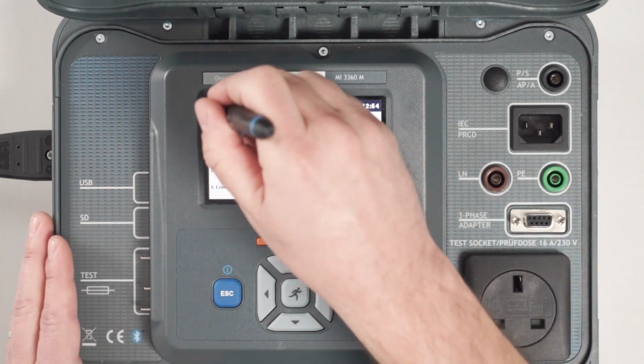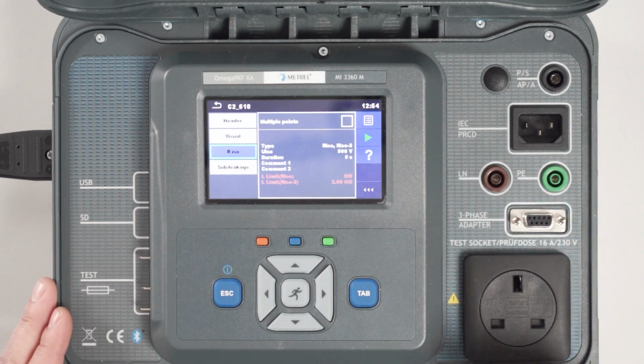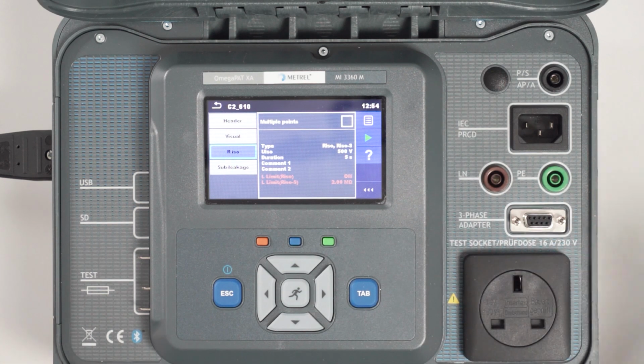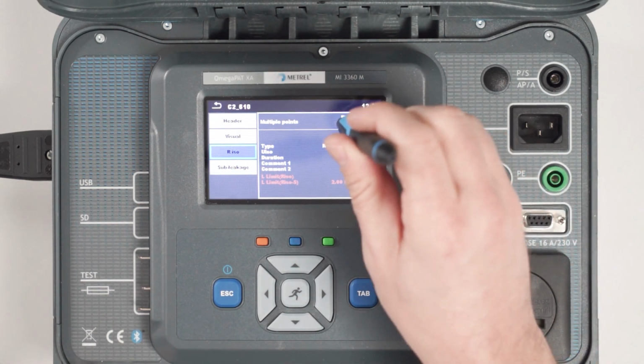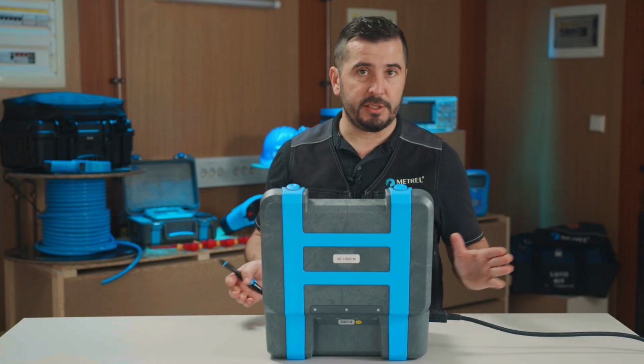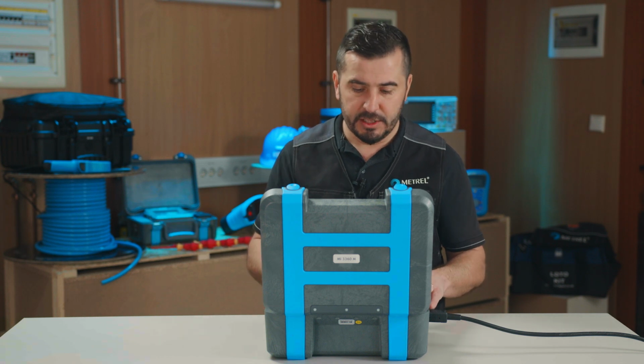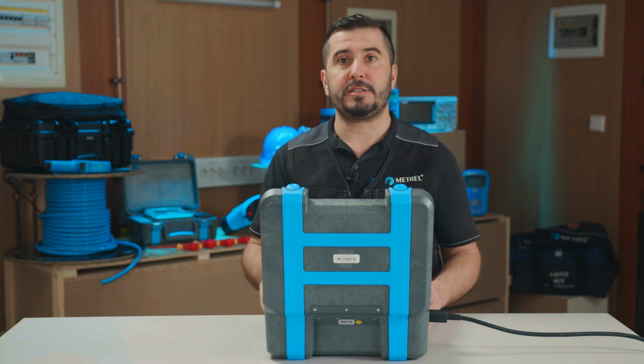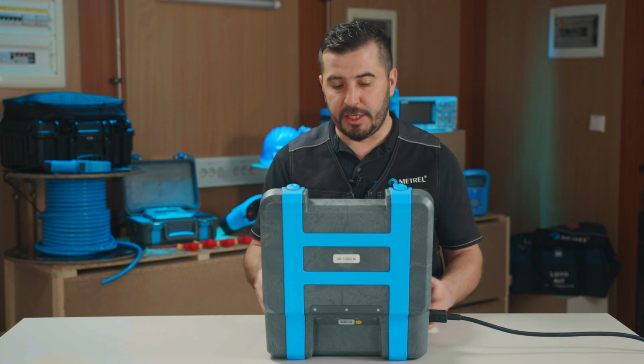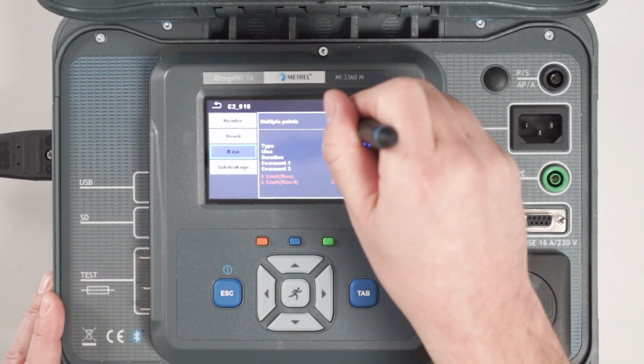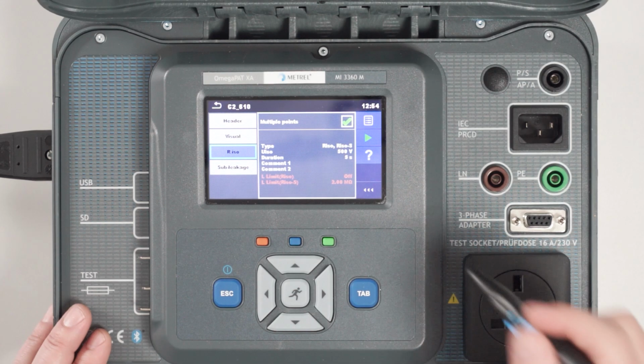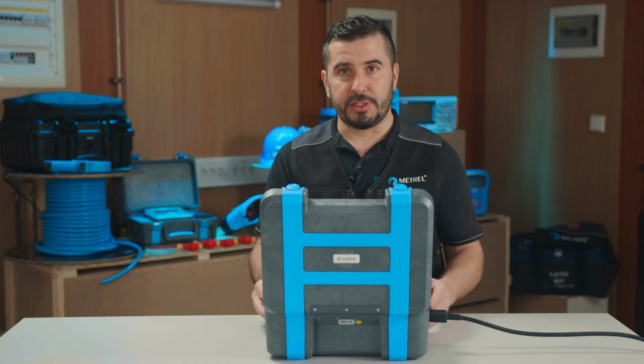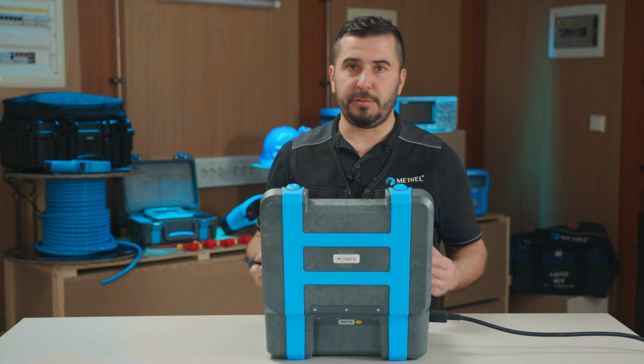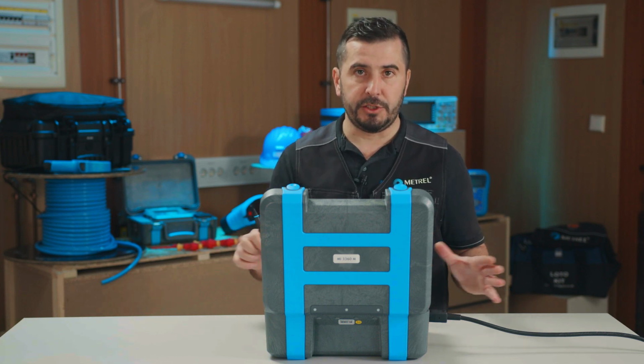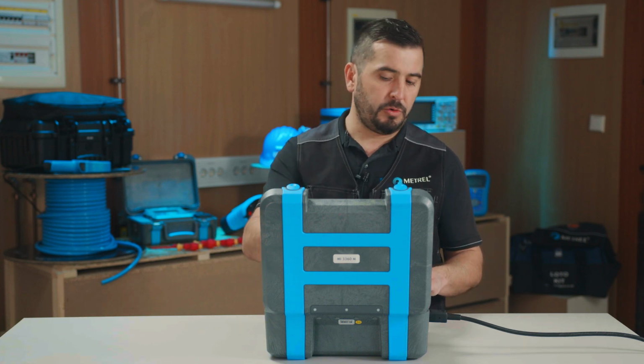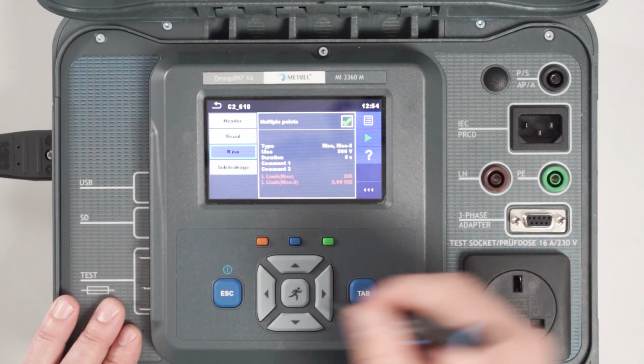So once we set all limits accordingly, there is also this multiple points option. This is also explained in one of our how-to videos when we are testing an extension cable on a reel. If we select the multiple points option, the insulation resistance test will repeat as many times as we want until we finish it by ending the loop. So we can also show this here with this particular example.